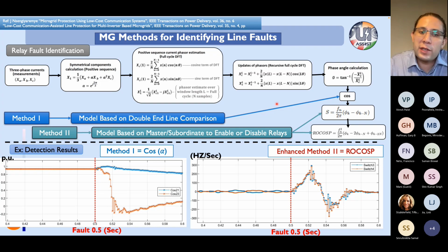So the first method implemented, basically we obtain the phase angle, so we calculate the phasors, and we identify the cosine of the angle. So we were able to identify that when we have a fault, we have a shift of the current. So that means the positive sequence cosine of angle changes direction, and that creates a method for detecting it, passing from positive into negative or from negative to positive per unit, because it's a cosine factor.